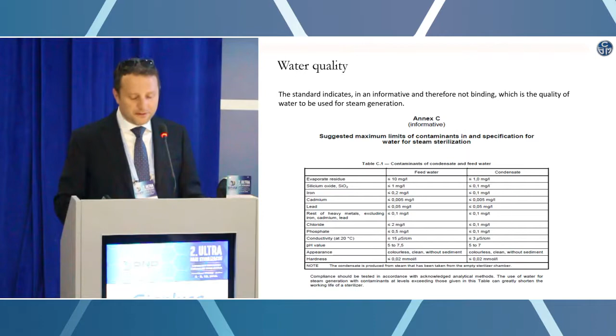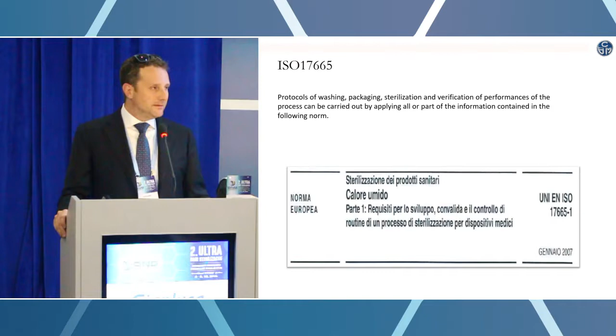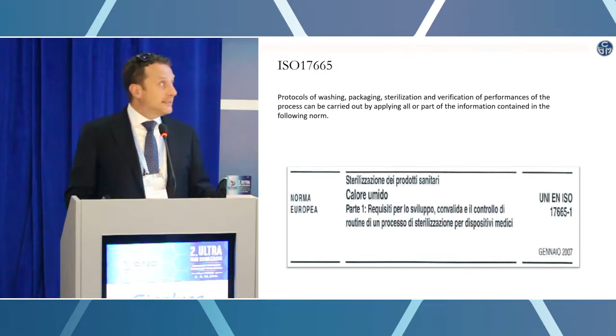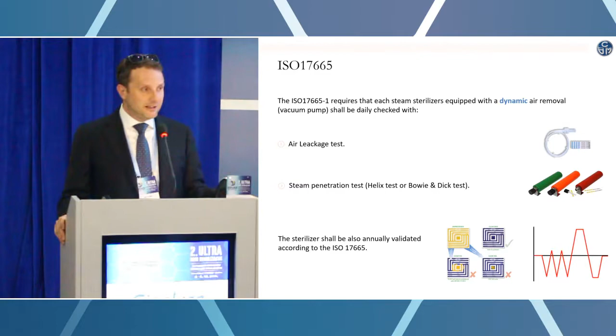Another important aspect to understand, speaking about the steam sterilization process, is that the steam sterilizer, as we talked about this morning, should be checked every day. There is a specific norm, ISO 17665, that asks you to carry out daily at least one air leakage test, which we can call a vacuum test, and the steam penetration test, that is a Bowie-Dick test at least, or you can do a Bowie-Dick test and a helix test, as we talked about this morning. Another important thing is that each sterilizer, even the small ones, should be validated on a yearly basis. So a dedicated company should come and prove that your sterilizer is still working properly, as it did when you purchased it.